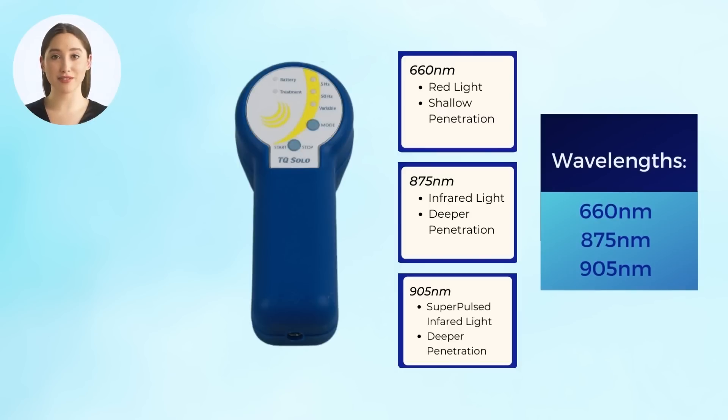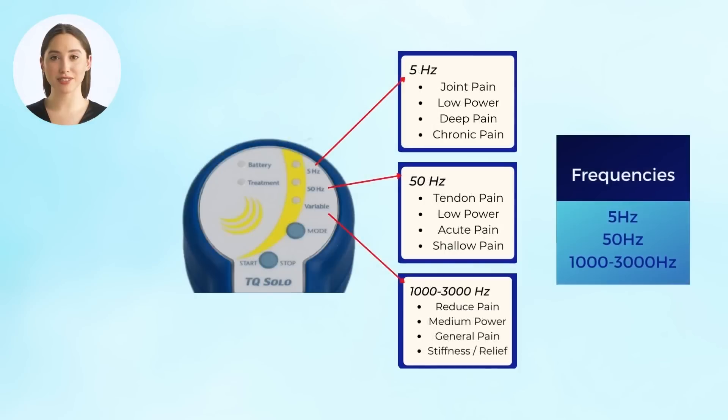The device also has three modes or frequency options. The lower the frequency, the deeper the laser will penetrate. 5 Hz is meant for deep chronic pain, 50 Hz is for tendon and shallow pain, and the variable setting, 1,000 to 3,000 Hz, is meant for superficial stiffness and general pain management.